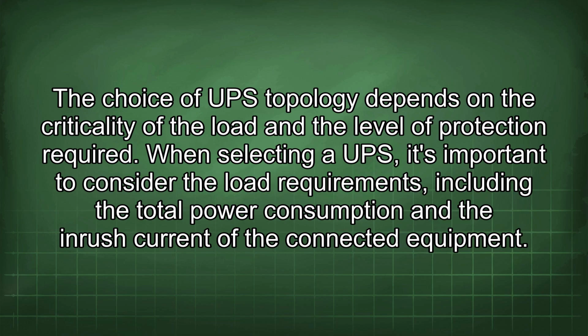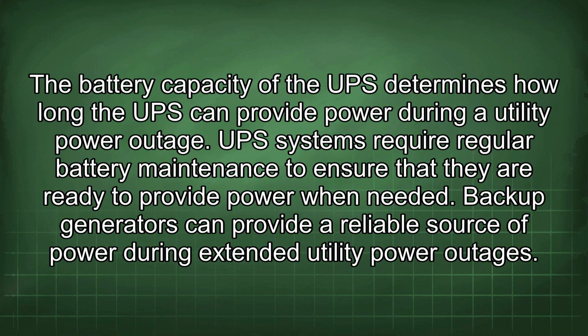When selecting a UPS, it's important to consider the load requirements, including the total power consumption and the inrush current of the connected equipment. The battery capacity of the UPS determines how long the UPS can provide power during a utility power outage. UPS systems require regular battery maintenance to ensure that they are ready to provide power when needed. Backup generators can provide a reliable source of power during extended utility power outages.